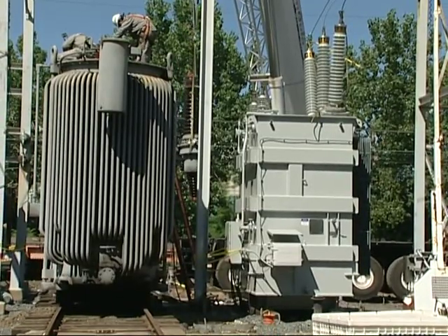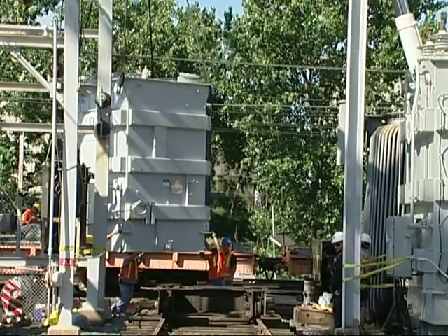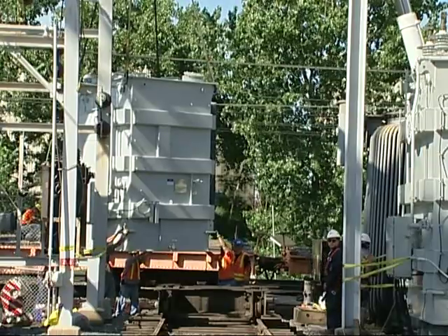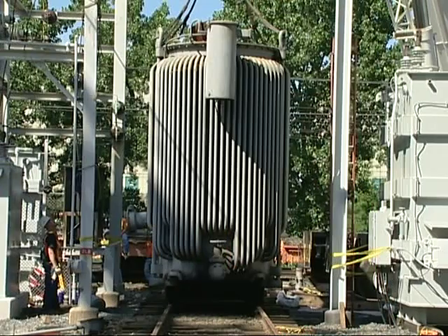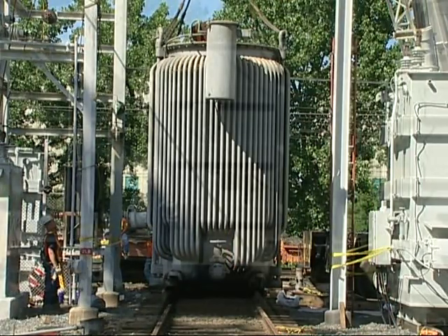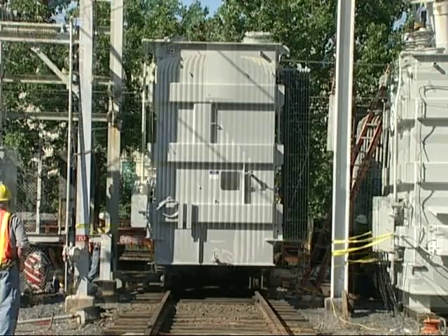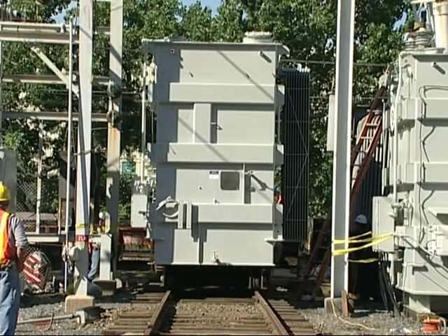We're here at sub 42 as part of the process of replacing the last of the four transformers here. In the process, we replaced not only the transformer, but the low side breaker, the high side switch, and replaced the old mechanical relays with a solid state relay that gives us a time and date stamp for any outage, plus trending analysis for voltage and current. It's a great improvement for analyzing issues on the railroad, or looking at load flow information when we put new trains on or add trains into the schedule.